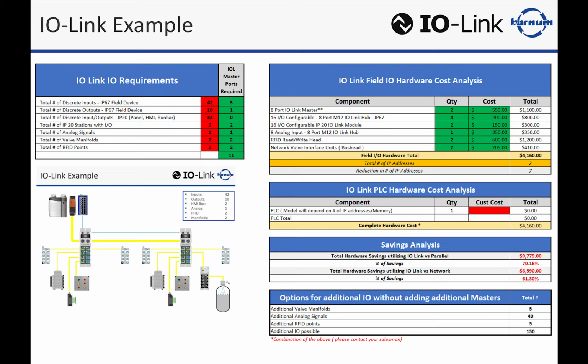So now, in the past and with a lot of our competitors to Balluff, for instance, 8 master ports would equate to 16 IO points per port. Well, in this case, since we can double that up, we get a 16 input block first. We use the last port, so we lose 2 IO points. Daisy chain to another 16 IO block, so we can actually get 30 IO points off of one single master port. That's right. So yeah, that's a little more advanced, but very easy to do, very simple.